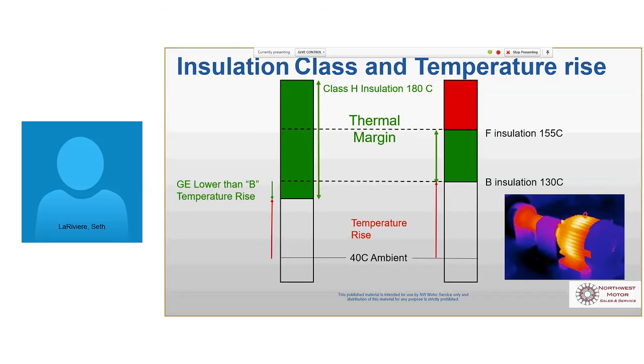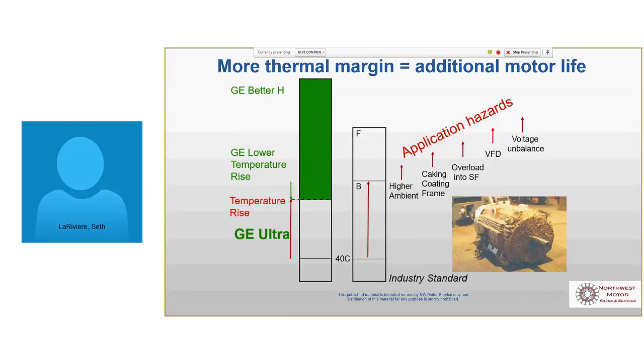So here's another slide, another motor caked in all kinds of dust. These are just real world application issues that you always deal with. Sometimes the ambient is higher than 40 degrees. Sometimes there's some kind of foreign material all over the motor. It might be pulp stock. It might be some kind of dust. Maybe they're running the motor over its designed load. So it's a 50 amp motor and they're running it at 54 amps, so it gets a little hotter. Maybe it's run on a VFD, or maybe your line isn't balanced right. Each leg isn't the same voltage. All those things introduce heat into the motor. So the more margin you have to deal with that, the better off you're going to be.